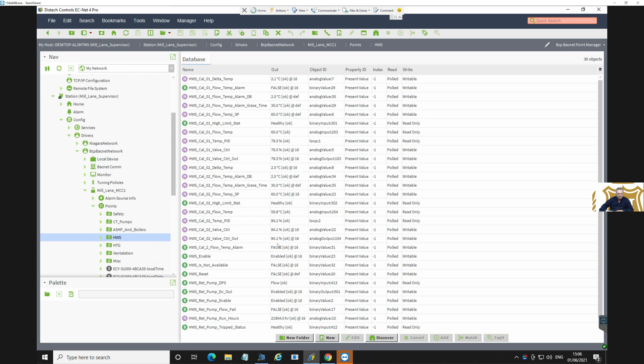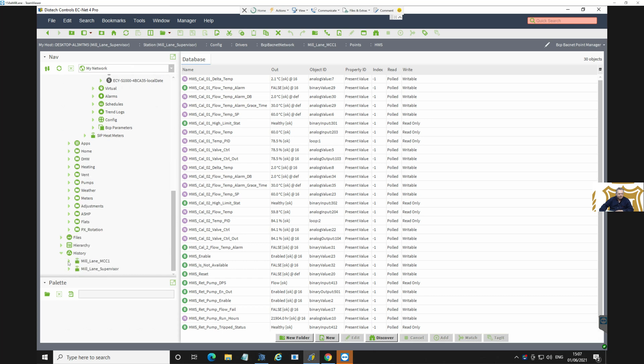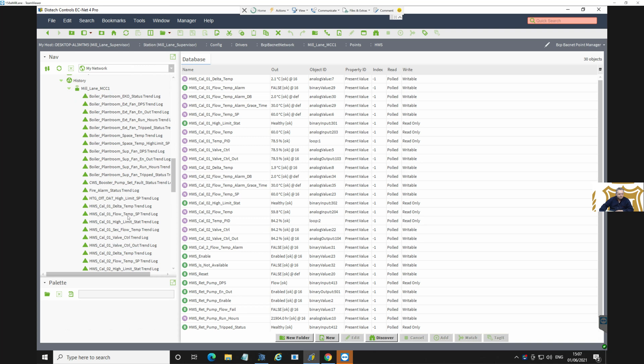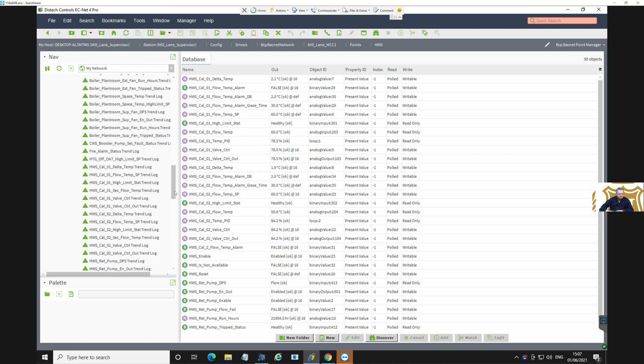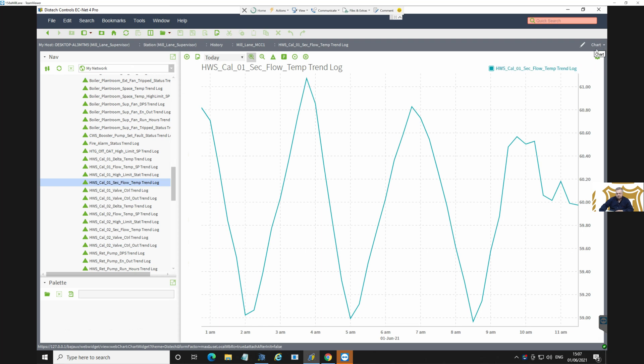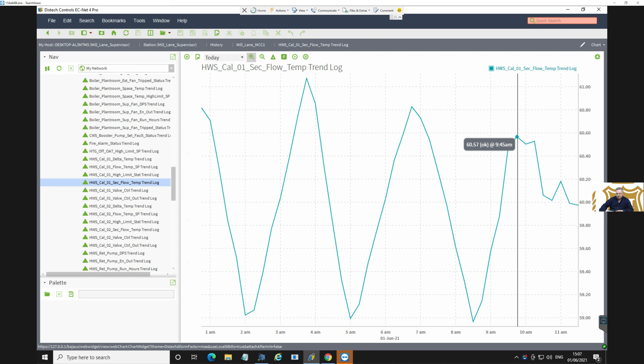Flow temp 59. While we're in here let's have a quick look at the history and see whether we've had any issues with the flow temperature. That's the valve, that's the setpoint. Secondary flow temp - it's a bit up and down. Around 11 a.m. - that's actually not that bad when you look at it. It's just between 59 and 61.